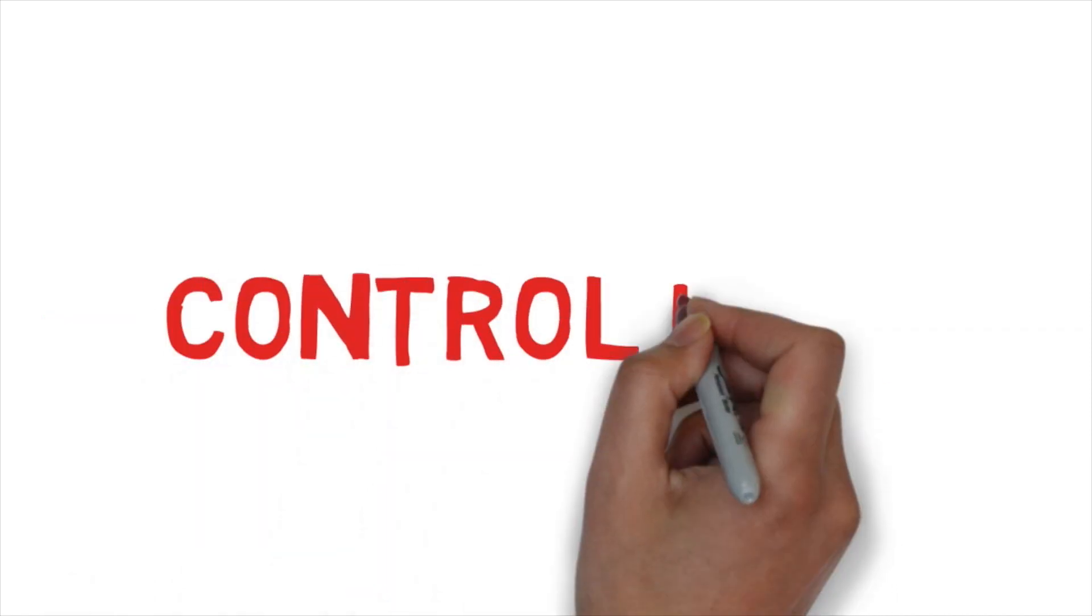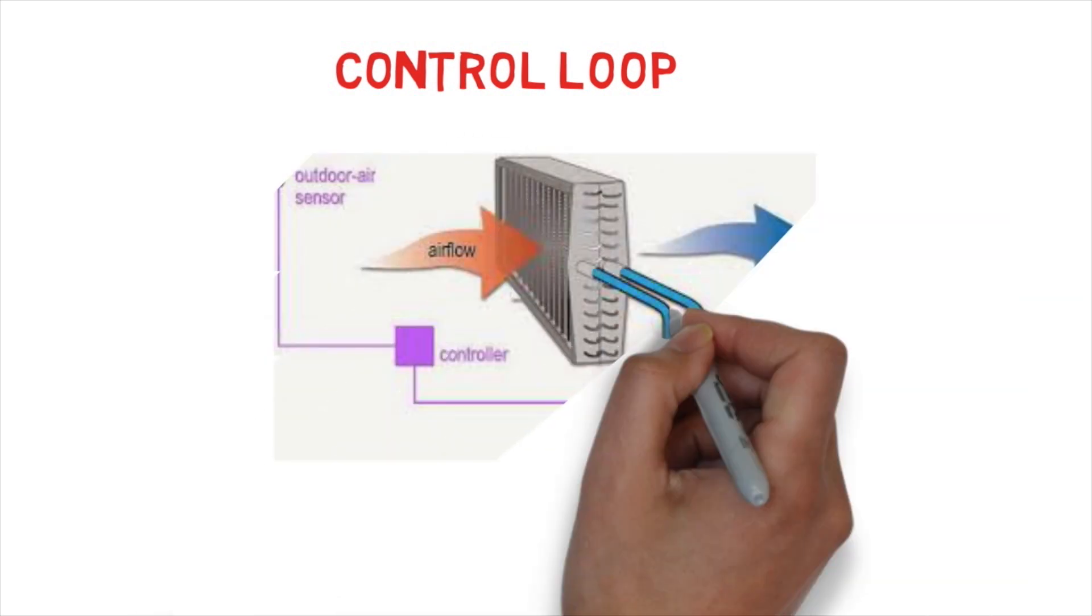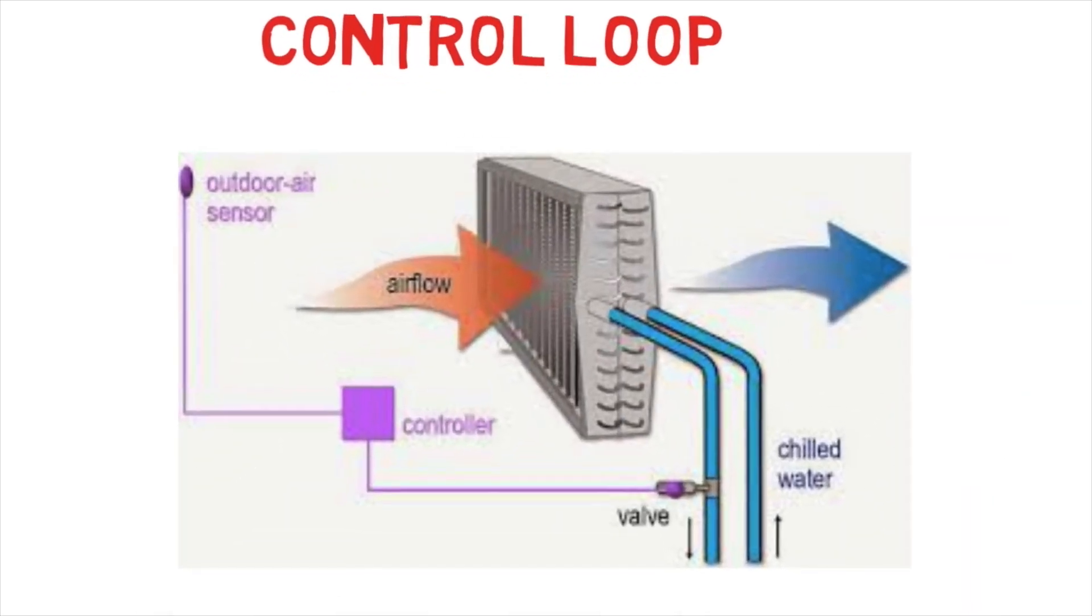First, we need to understand what comprises a control loop. There are three elements: the sensor, the controller, and the controlled output, which is typically a valve or a damper in HVAC. The sensor is usually testing something like temperature. The controller allows us to create a set point, and then based on how close we are to set point, a signal is sent out to the actuator that controls the valve or the damper.